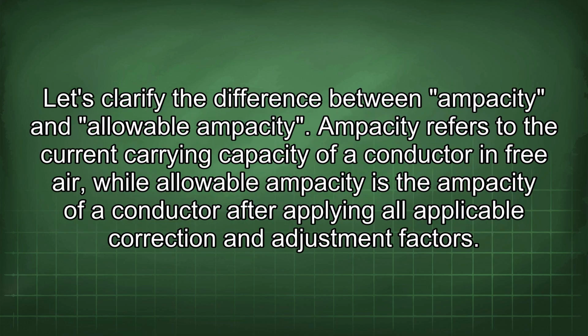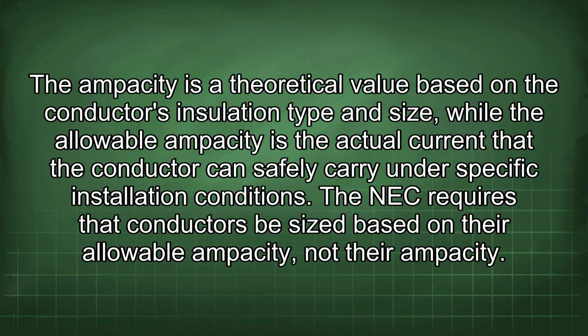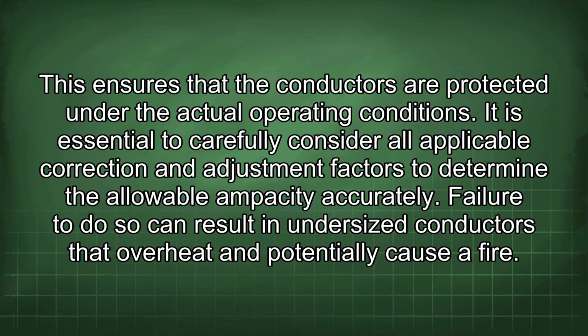Let's clarify the difference between ampacity and allowable ampacity. Ampacity refers to the current carrying capacity of a conductor in free air, while allowable ampacity is the ampacity of a conductor after applying all applicable correction and adjustment factors. The ampacity is a theoretical value based on the conductor's insulation type and size, while the allowable ampacity is the actual current that the conductor can safely carry under specific installation conditions. The NEC requires that conductors be sized based on their allowable ampacity, not their ampacity. This ensures that the conductors are protected under the actual operating conditions. It is essential to carefully consider all applicable correction and adjustment factors to determine the allowable ampacity accurately. Failure to do so can result in undersized conductors that overheat and potentially cause a fire.